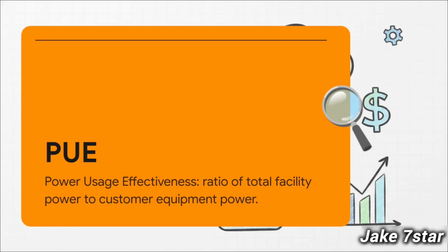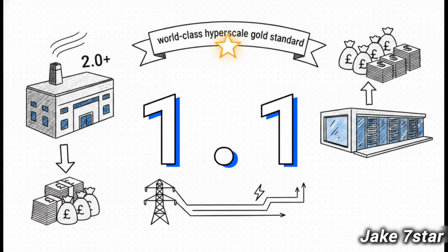Because heat is so expensive to manage, the industry obsesses over one metric: PUE, or power usage effectiveness. A perfect PUE of 1.0 would mean every cent spent on electricity goes directly to powering the servers, with zero waste on overhead like cooling, fans, or lighting. In reality, older facilities often run at a terrible 2.0 or even higher, wasting as much power as they use. But the hyperscale gold standard today is 1.1.